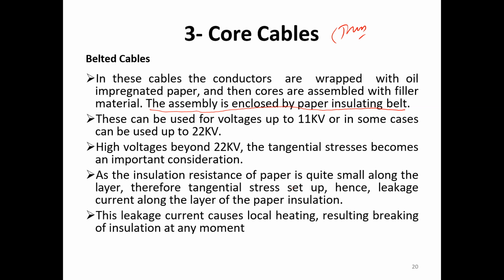Then for high voltage beyond 22 kV, the tangential stress becomes an important consideration, as the insulation resistance of paper, which we use in belted cable for insulation, is quite low. The layer therefore sets up tangential stress, hence leakage current along the layer of the paper insulation.